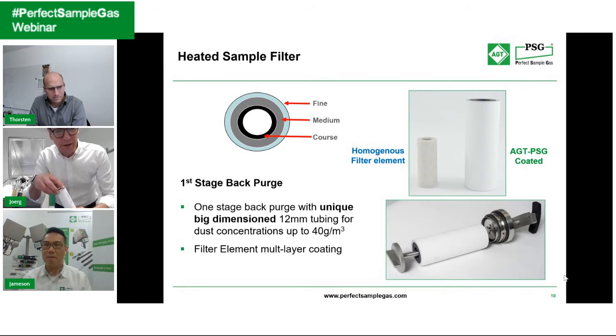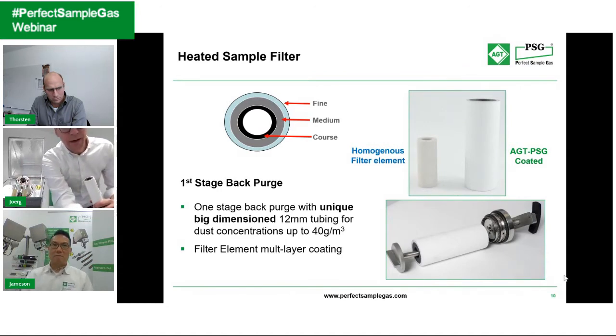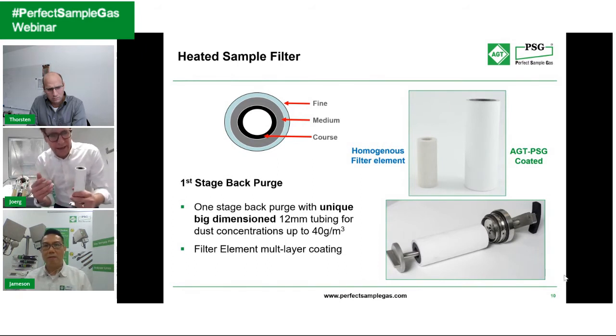Now, if we remember the P&ID you just shared, Jameson, and consider now the filter element - especially in gas-fired power plant applications, as Thorsten mentioned, the dust level is not very high, but there's still some dust. As soon as you get some blockage, which happens faster with a smaller filter element, the entire emission monitoring system changes because of different pressure situations. That means if the filter is blocked, you have a different pressure.